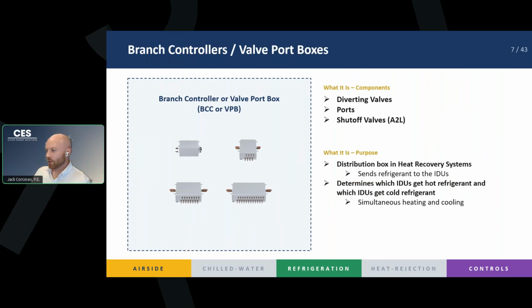And what do our branch controllers and valve port boxes do? We're talking about our heat recovery systems. These are the devices that distribute the refrigerant to the zones that need it. It's essentially a box with a handful of valves that open and close depending on which zones and which indoor units need heating, cooling, or how little heating or cooling they need. It has a certain number of ports, and every indoor unit needs its own dedicated pair of ports. There are various sizes by various manufacturers, but they generally come in 1, 4, 8, and 12 ports. Some manufacturers have more, some just have 1 or 4. Essentially, the number of ports dictates the number of indoor units. So if you have 4 ports, you have 4 indoor units that it can distribute the refrigerant to.